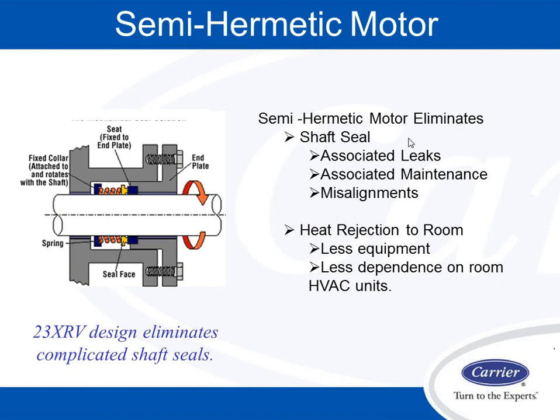Semi-hermetic motor. The motor is refrigerant cooled, so it's going to operate in the ambient temperature of the refrigerant, about 85 degrees, whereas an open drive machine can operate in higher ambient temperatures. It doesn't have a shaft seal, which means no associated leaks and no changing of the shaft seal later on in its life. Again, it's an overall life cycle chiller.